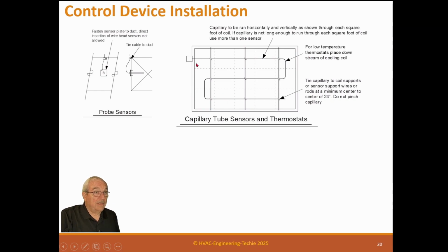Or I've seen them take it through a conduit in there and just wrap it around the conduit. That doesn't average anything. And really what I always laughed about is every single sensor you buy comes in a little cardboard box. And you pull out the sensor and there's a piece of paper in there. It's the instructions on how to install it.